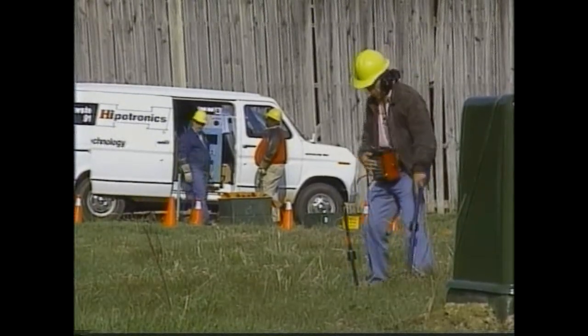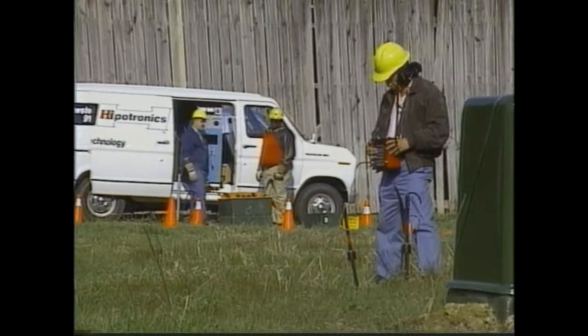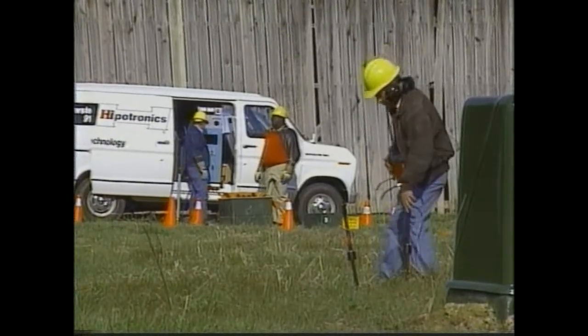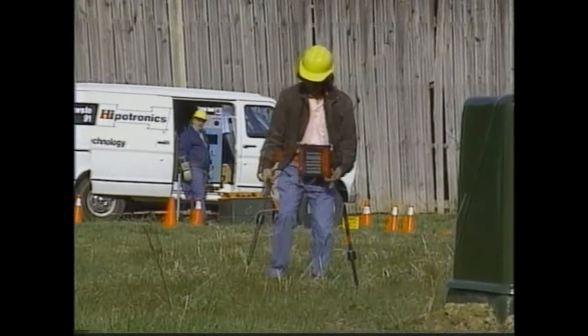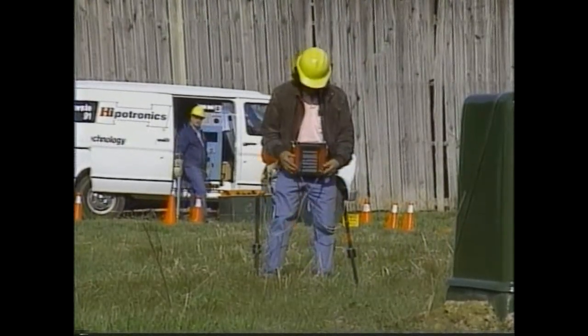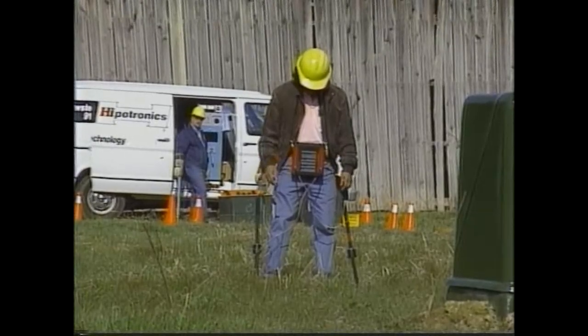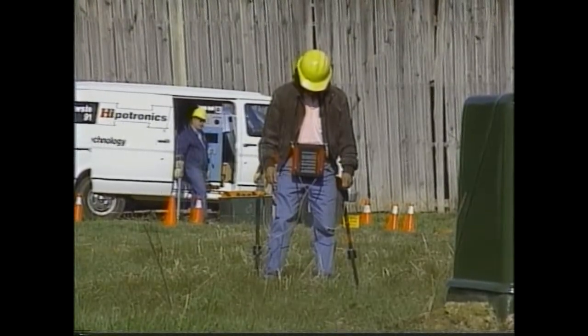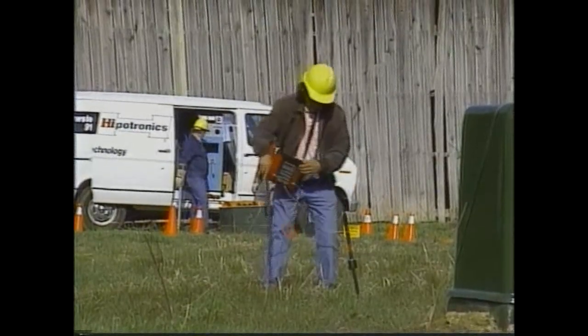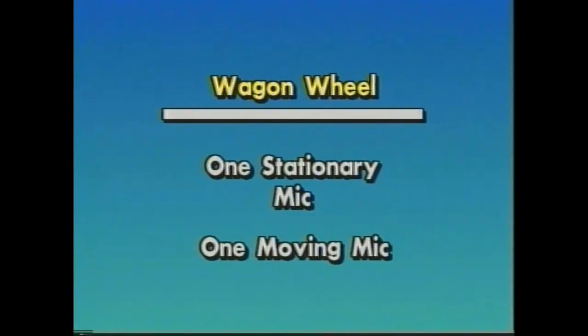To make sure that I have located the fault, I can do a 90-degree walk around just like I did in earth gradient fault locate. When I can place one probe in a stationary spot and move the other probe through the 4 walk-around positions, and the meter is always tripping towards the center probe, it's time to mark the fault and shut the thumper down. When doing a wagon wheel locate, leave one microphone sitting in one spot and move the other microphone back and forth until a movement of 1 or 2 inches will provide a reverse reading. If 1 or 2 inches can produce the reversal, the spoke in the wagon wheel will be very close to being dead center.